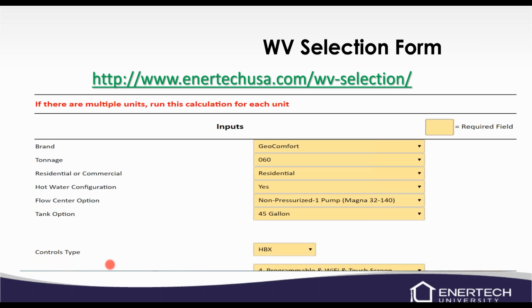It'll ask you if you're going to do hot water configuration. That's a yes or no. And then the type of flow center. We have a non-pressurized single pump variable speed flow center, and we have a pressurized flow center, variable speed. To me, it doesn't matter if it's non-pressurized or pressurized. That's usually a preference. I've used a lot more pressurized, so I prefer pressurized. A lot of people prefer the non-pressurized due to air and that kind of thing. To me, it doesn't matter. It's not going to affect the unit, but just choose which one you want.